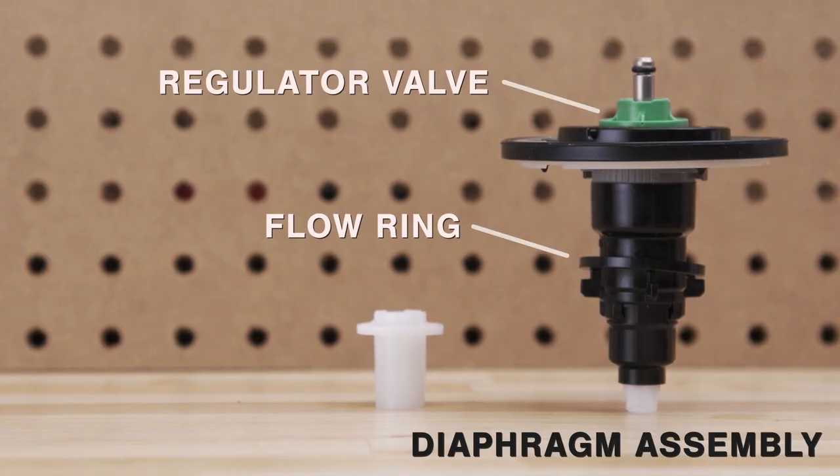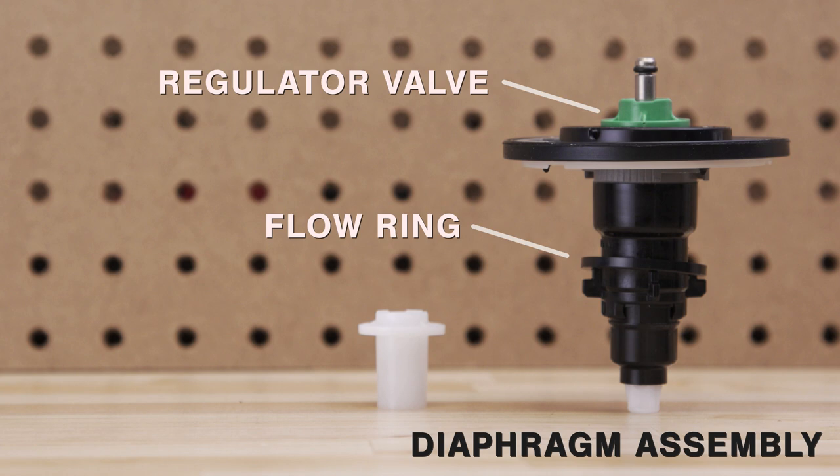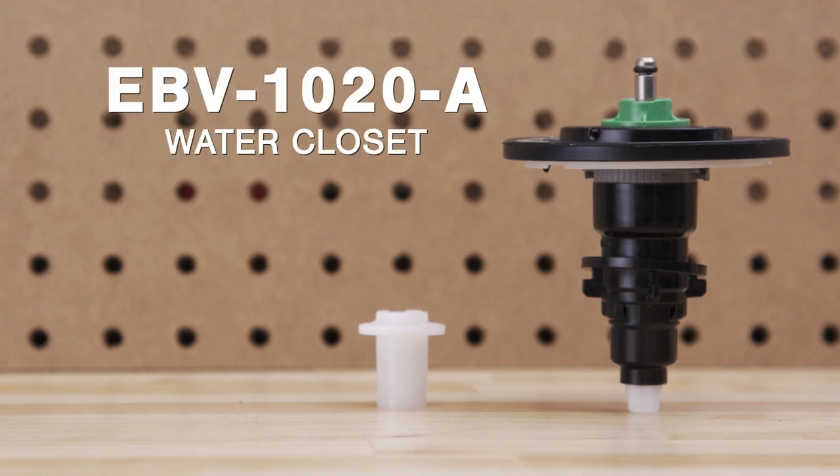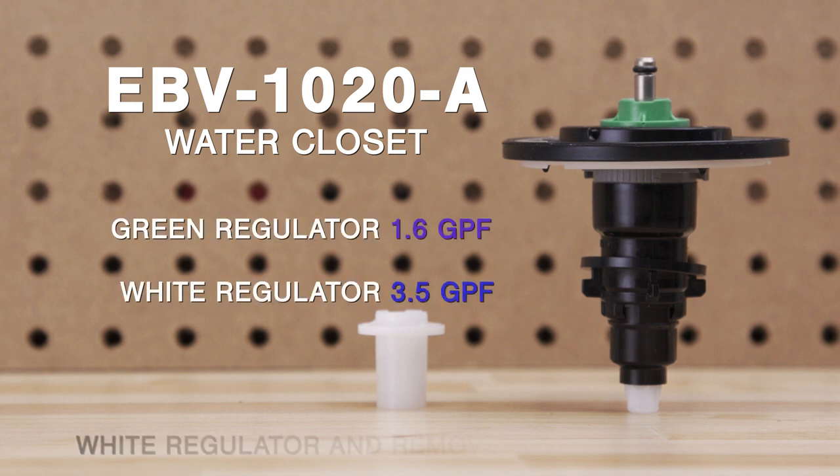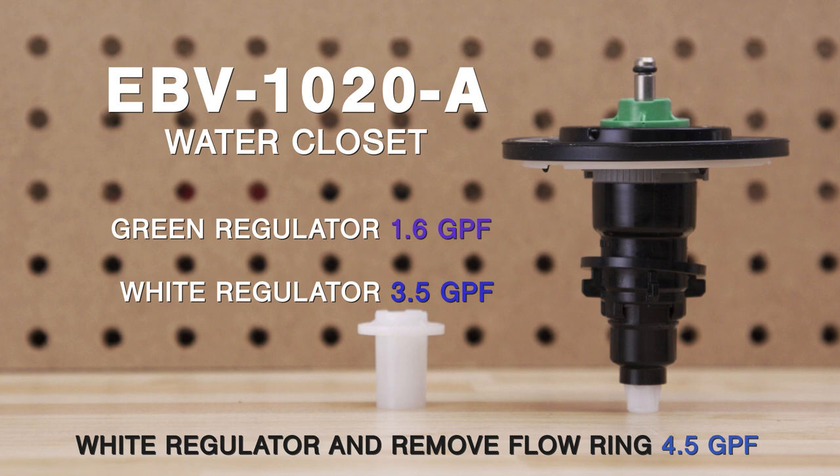The flush volume is controlled by both the flex tube diaphragm assembly and regulator. Regulators come in different heights and will change how much the diaphragm opens during each flush. White regulators create a higher flush volume. Green regulators create a lower flush volume and are commonly found in water-saving units.